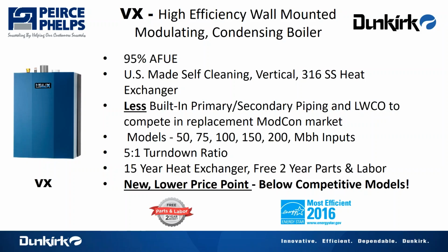Modulating condensing boilers are 15 to 18 years old now, when we start seeing a pretty substantial replacement market. You're not going to need to go out and sell a VLT boiler when we're replacing an existing modulating condensing boiler because the primary, secondary, near boiler piping and pumping is already set up. So we really just need a boiler that's going to hook up to that existing primary, secondary loop.